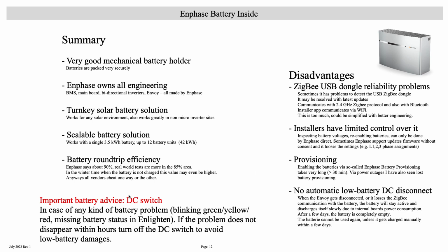Important advice for the DC switch: for any kind of battery problem, blinking green, blinking yellow, blinking red, continuous red, whatever, or if the battery is missing from the Enlighten status, so you don't see the battery in Enlighten, if this problem exists and won't disappear within hours, turn off the DC switch to save your batteries.